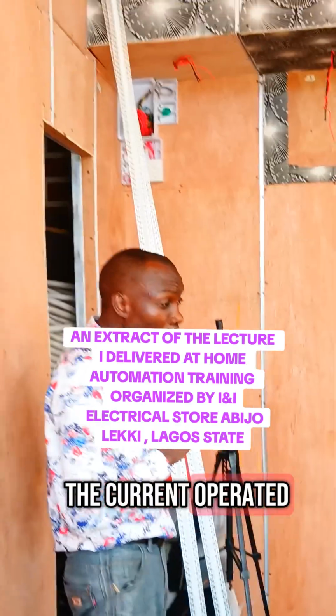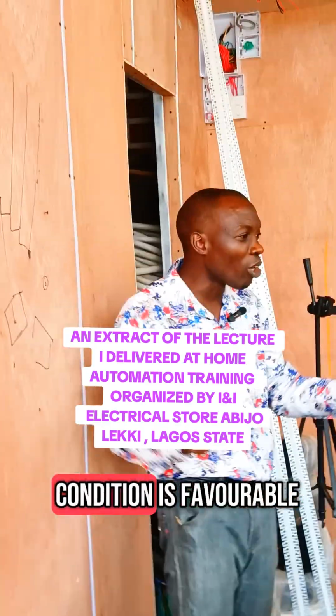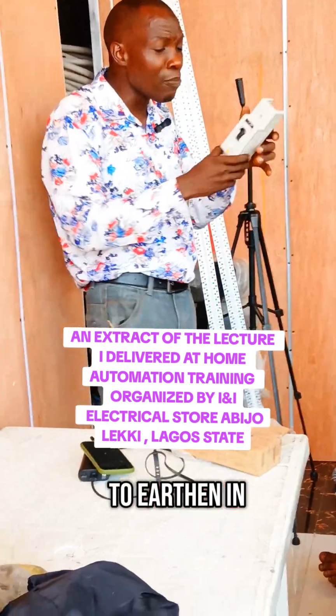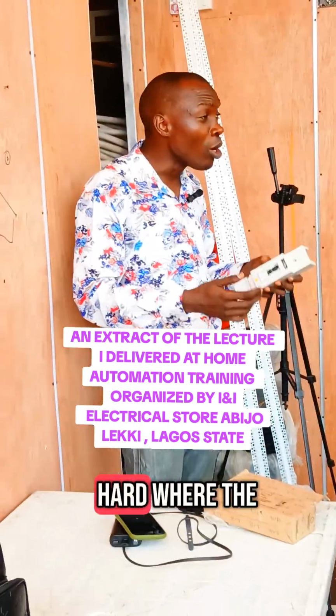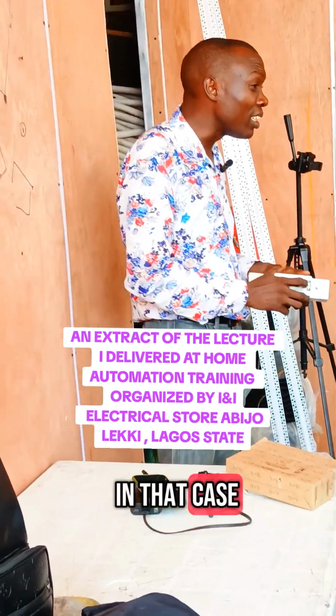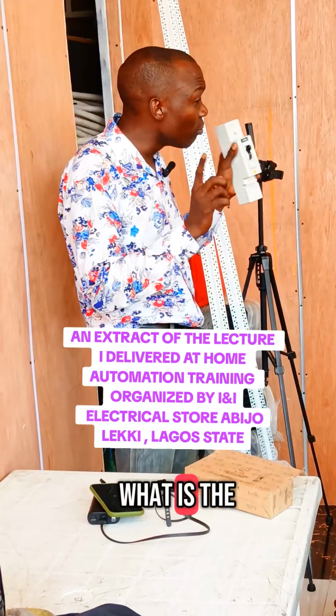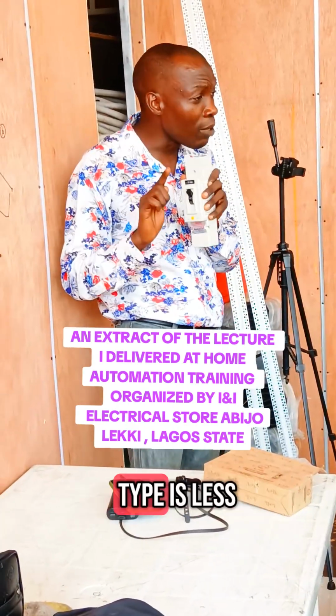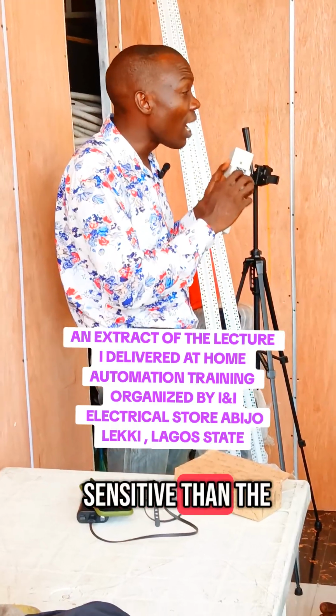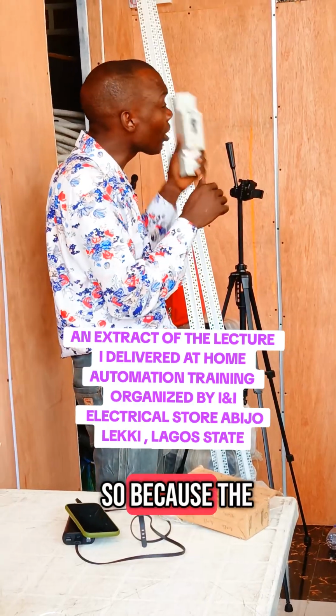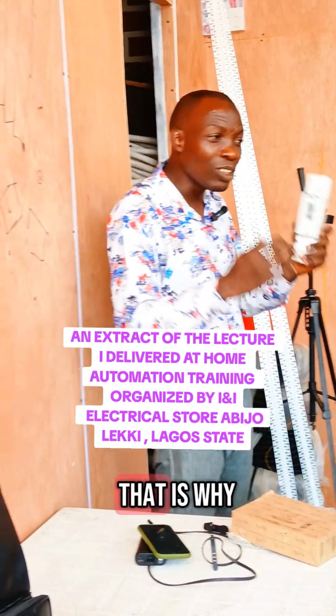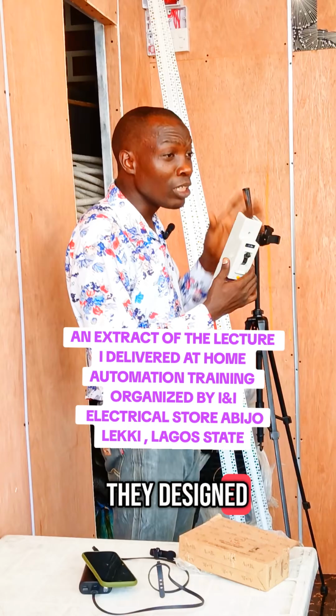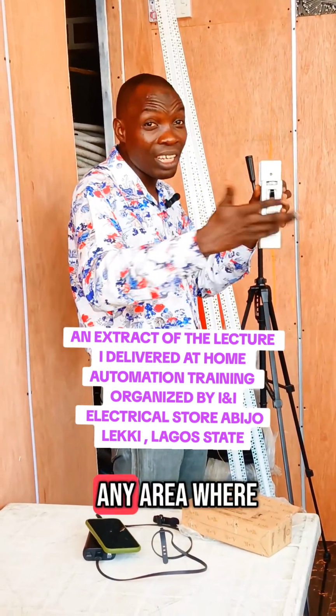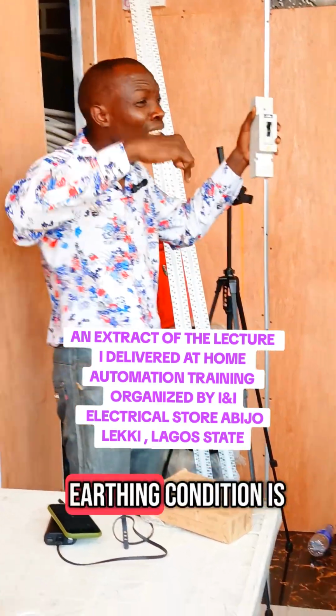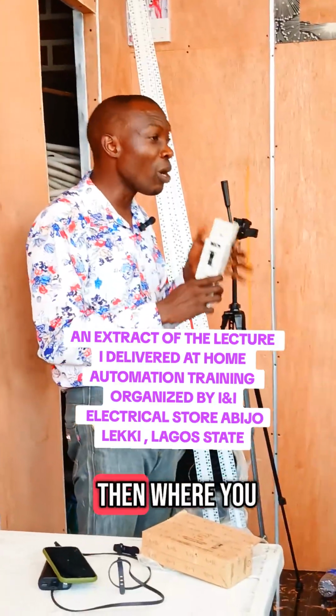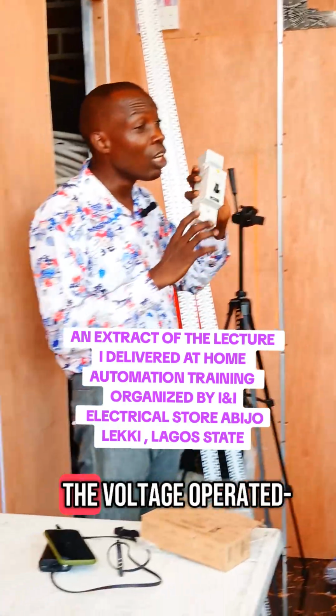So the current operated type is used where the earthing condition is favorable. If you need to earth in a place that is sandy, rocky, and so on, where the earthing condition is very poor, in that case, go for the voltage operated type. What is the difference between them? The current operated type is less sensitive than the voltage operated type. Because the earthing condition is very poor, that is why they designed the voltage operated type. But the current operated type, you can use in any area where you have loamy soil, clay soil and so on, where the earthing condition is very improved. Where you have a very poor earthing condition, you go for the voltage operated type.